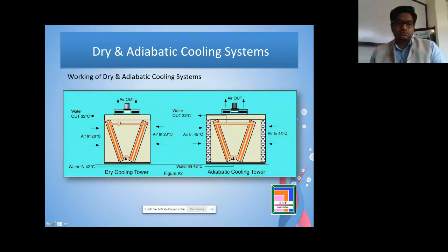It's like a heat sink, and the material of this heat exchanger can be aluminum fins, stainless steel fins, copper fins or cupronickel fins, with a heresite coating if we have to install this kind of thing on a ship. The principle is the water comes in at 42 degrees centigrade, the air is coming in at 28 degrees centigrade, and the water goes out at 32 degrees centigrade. So there is a constant dissipation of heat.